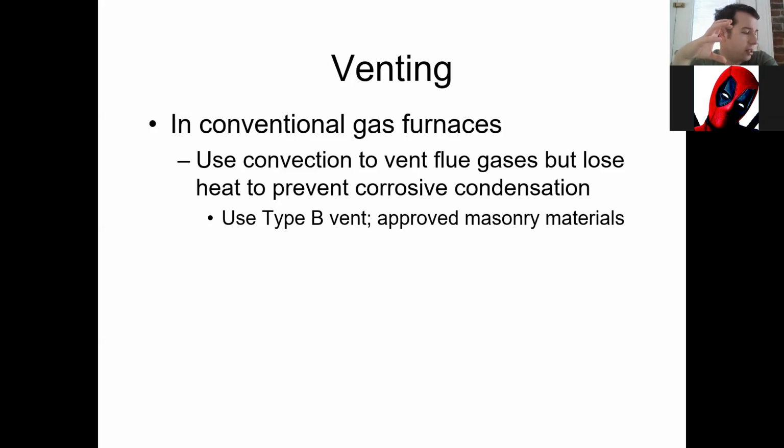That's got it where it's basically got these collars on the end of it that will actually lock on and will link together each section, so it makes it really nice. But the other thing is you have those collars because inside of that B venting is a smaller pipe inside of it. It's basically double walled. And because of that wall, that interior of the piping, you have to have where it fits on very snugly.